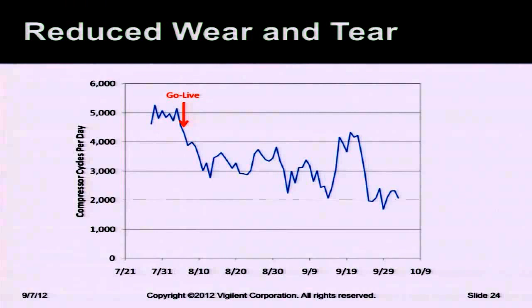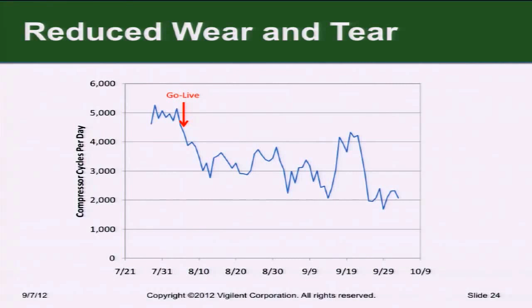The windings in the electric motors that drive these compressors also get a mechanical shock every time you turn one of these things on or off. When you turn it on, you get a surge of current, and that causes stress on the windings. And so what happens after a while, you get a little bit of mechanical friction. So every cycle is just doing a little bit of wear, a little bit of wear. Sooner or later, the windings get a short circuit and they fail. And it doesn't matter whether it's slow or fast. Basically, if it's designed for 200,000 cycles on average, then on average, if you're cycling at 5,000 a day, you're going to be 2.5 times faster to failure than if you're at 2,000. But that's not the end of the story.